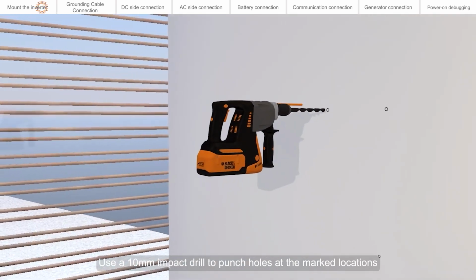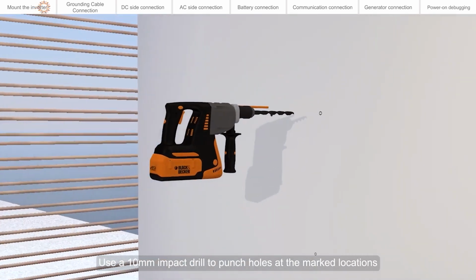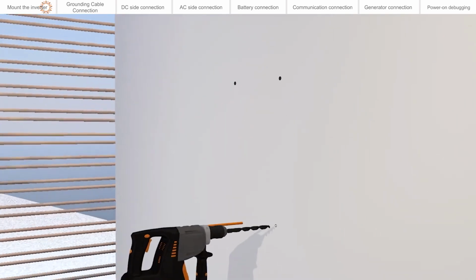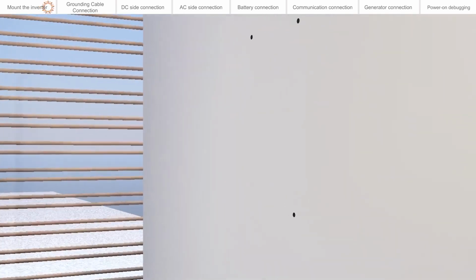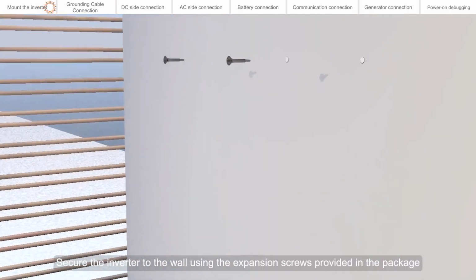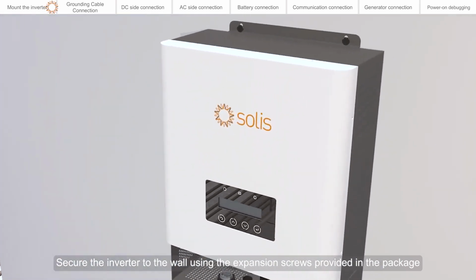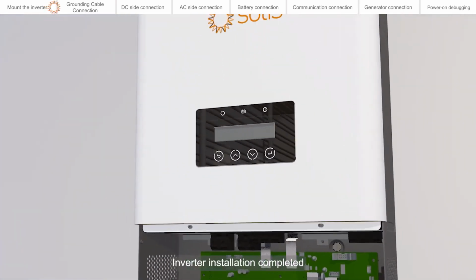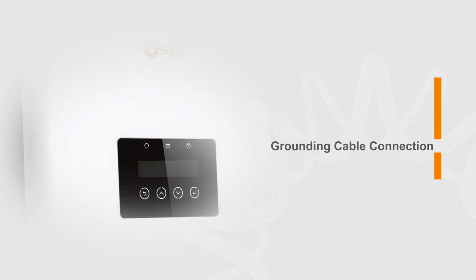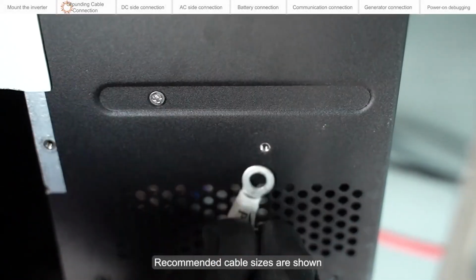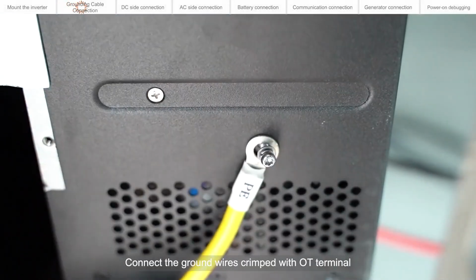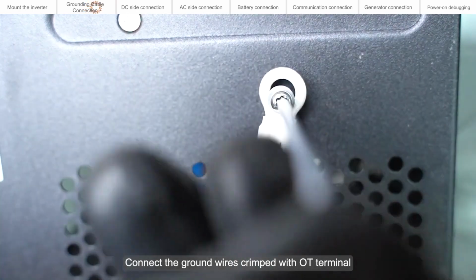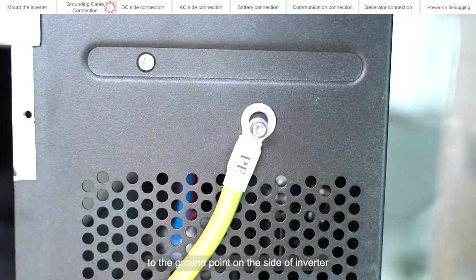Use a 10 mm impact drill to punch holes at the marked locations. Secure the inverter to the wall using the expansion screws provided in the package. Inverter installation completed. Recommended cable sizes are shown. Connect the ground wires crimped with OT terminal to the ground point on the side of the inverter.